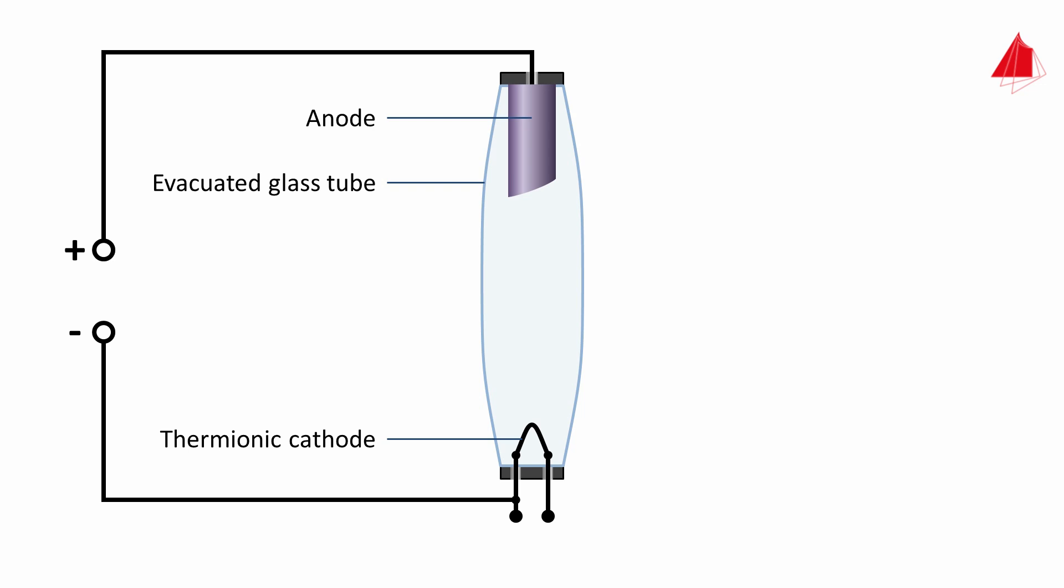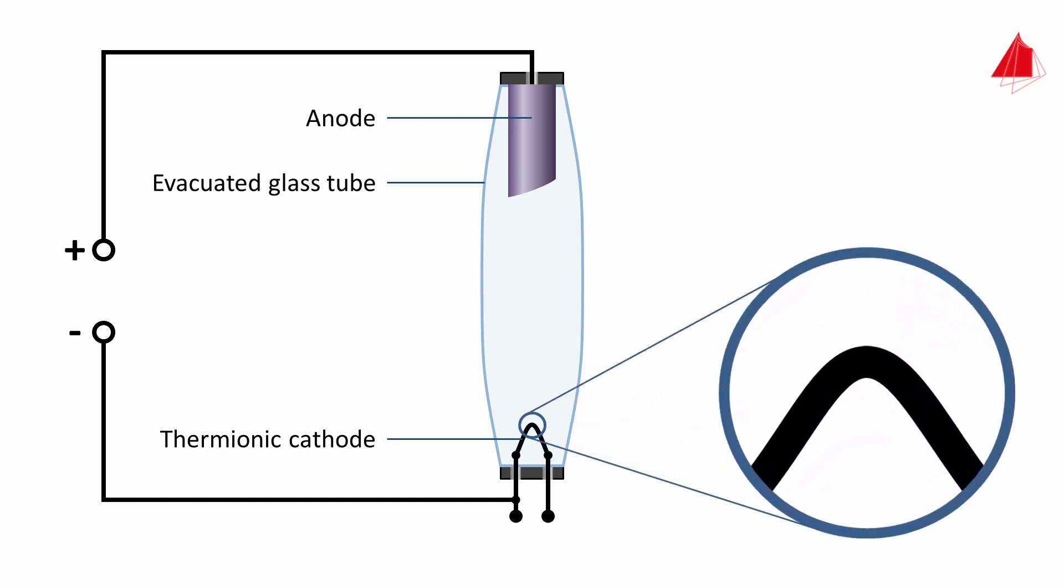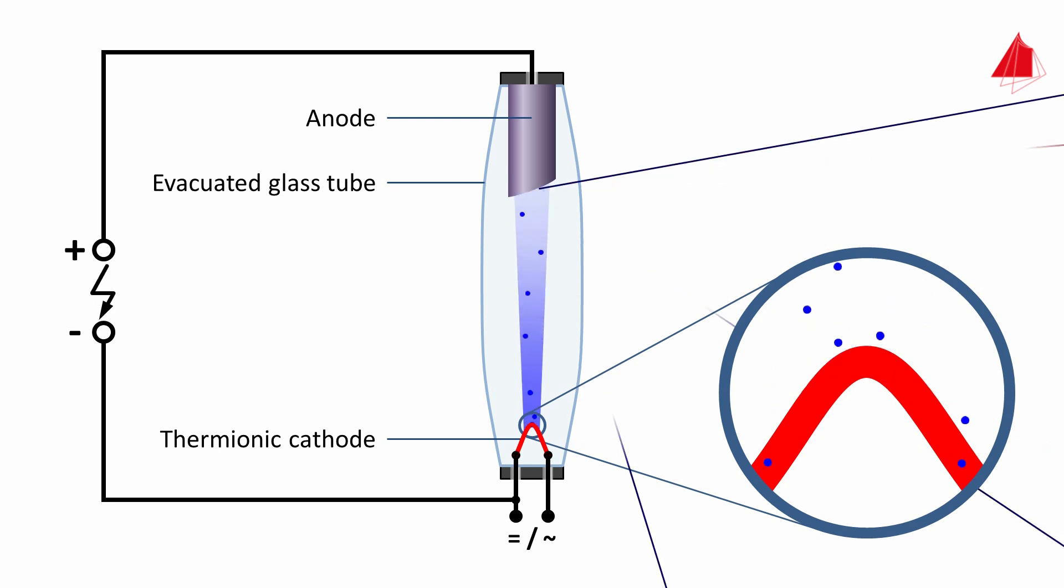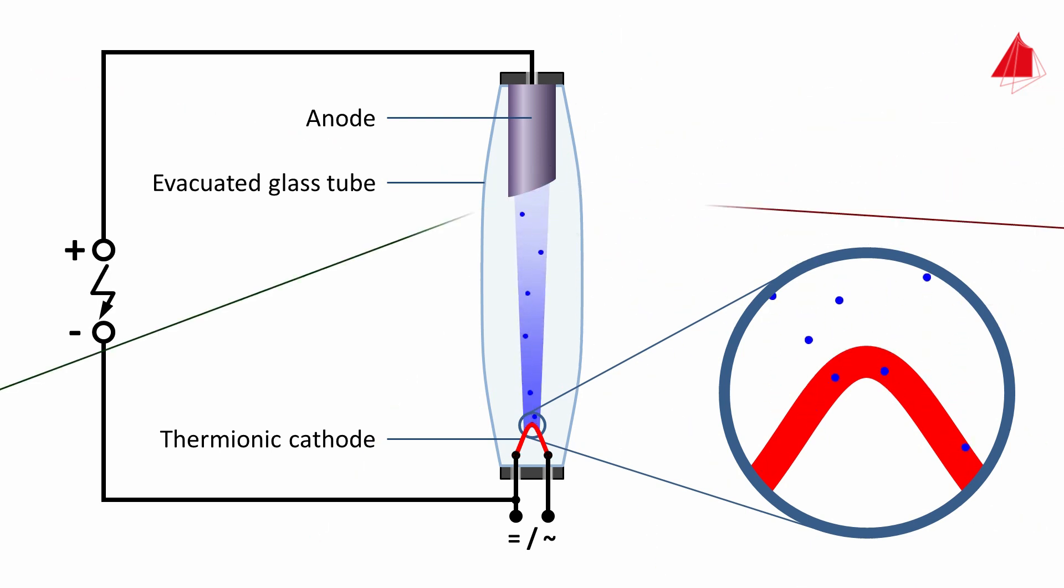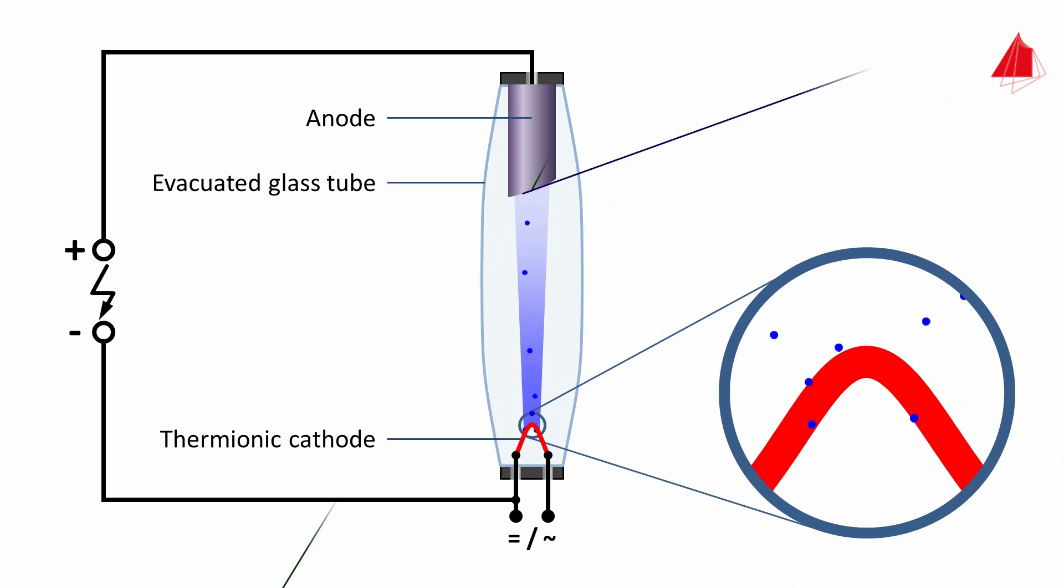The thermionic cathode is now heated up by an electric current. The thermal movement enables some electrons inside the wire to leave the surface. This is known as thermionic emission. By switching on the high voltage, a strong electric field between the thermionic cathode and the anode is created. This strong electric field accelerates the emitted electrons towards the anode.